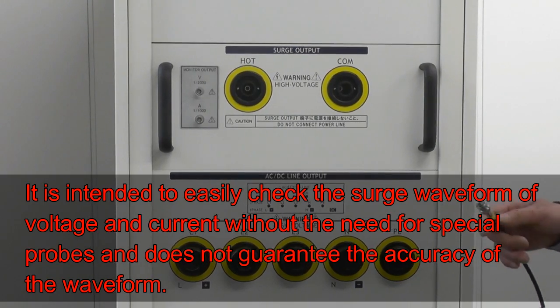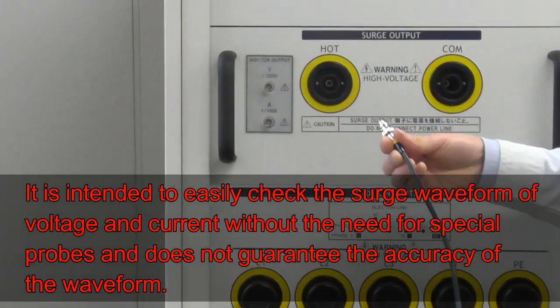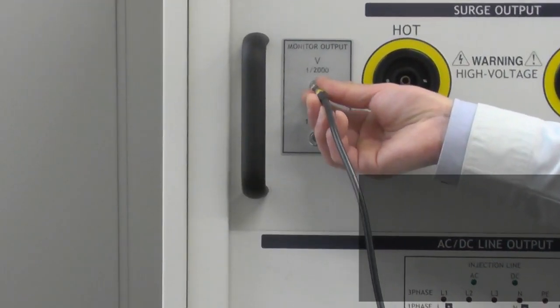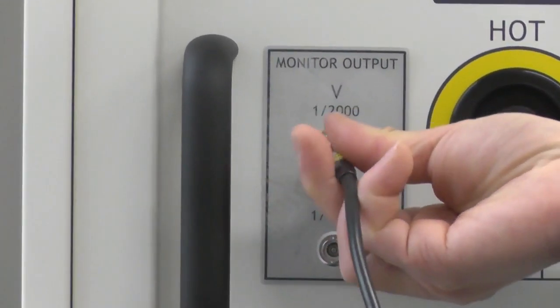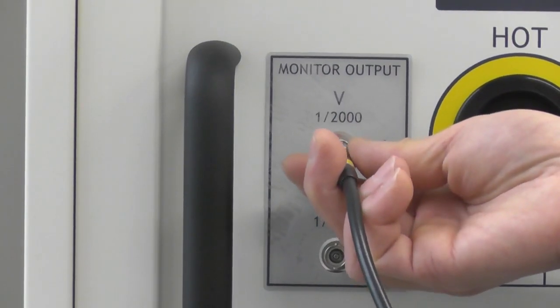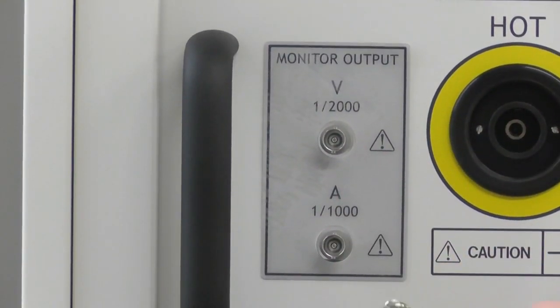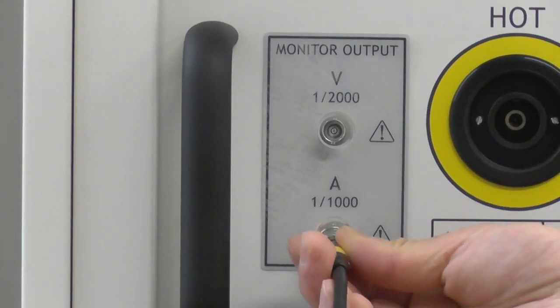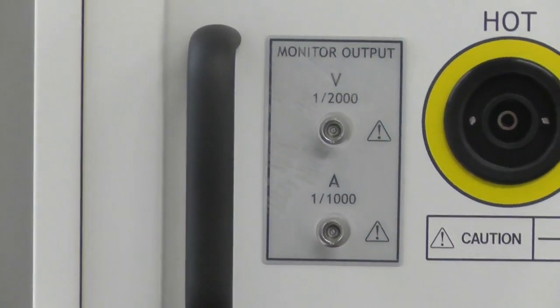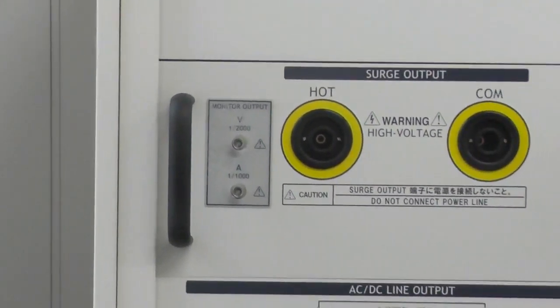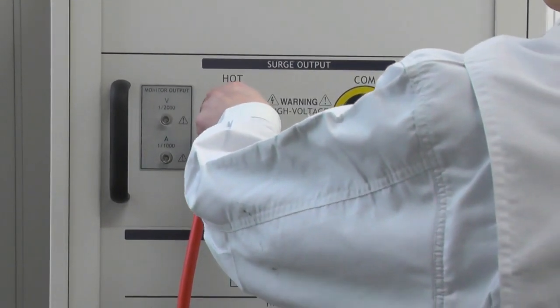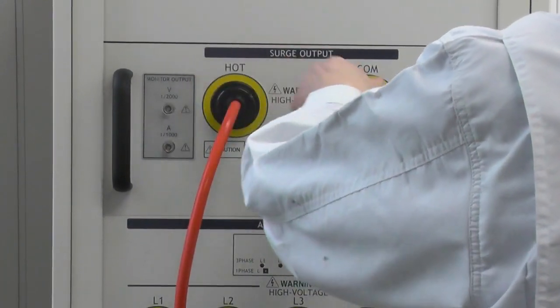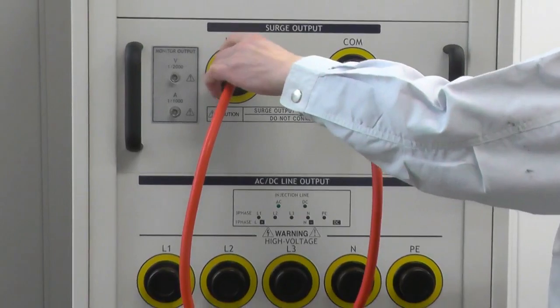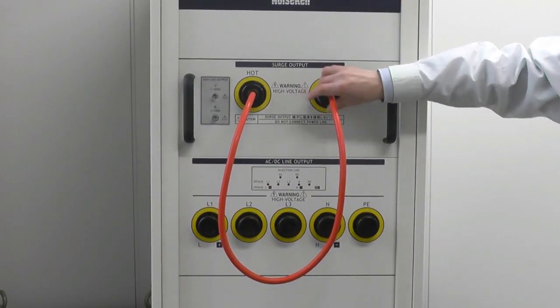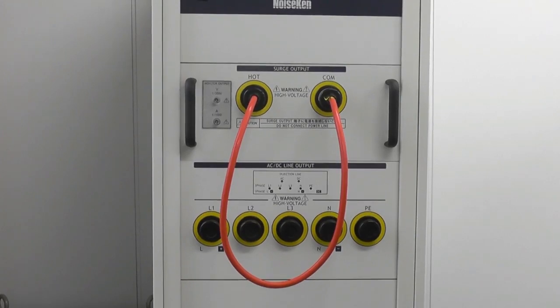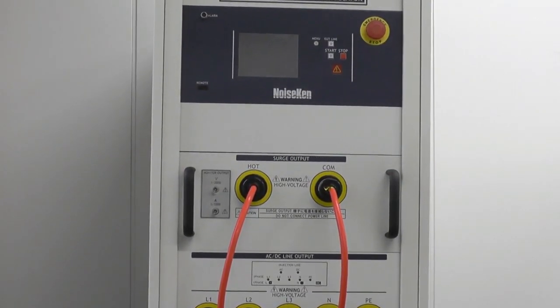Use the monitor coaxial cable. For voltage waveform observation, connect to the V terminals. And for current waveform observation, connect the I monitor terminals to the oscilloscope. And in this case, we have to short the hot and com in case of the current waveform observation. Then press the start button to observe the waveform with the oscilloscope.